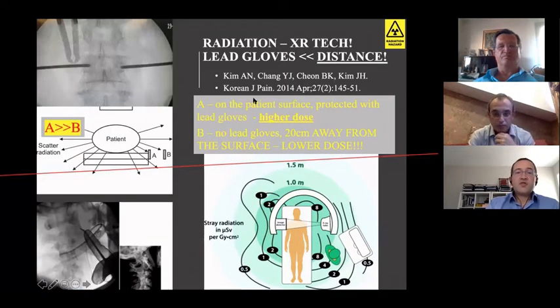This is very good research that I wanted to show you to demonstrate the importance of distance. This is Kim from Korea and team. They have done a very interesting study. They wrapped an X-ray detector with a lead glove and put it right on the patient, that is A. And then another detector that is away from the patient, only 20 centimeters away, and is not wrapped with the lead glove. They found that A has a significantly higher dose despite being wrapped with a lead glove, compared to B, which is not wrapped with a lead glove but is only 20 centimeters away from the surface. So this is a big drop of dose only by a simple measure, stepping one step back. And this is something that you have to implement in any possible case when you perform your surgeries.